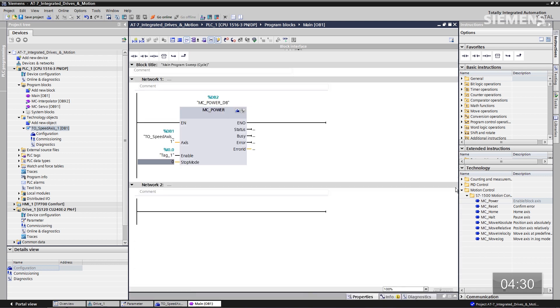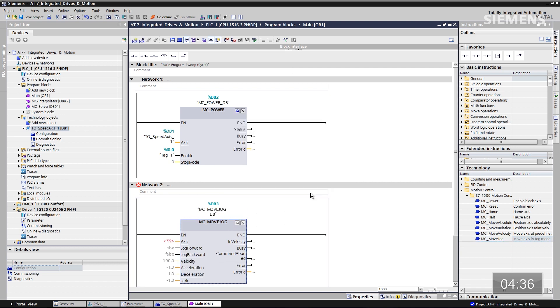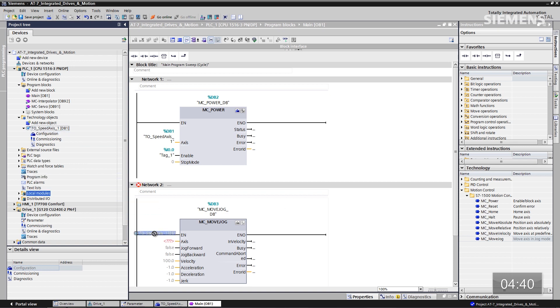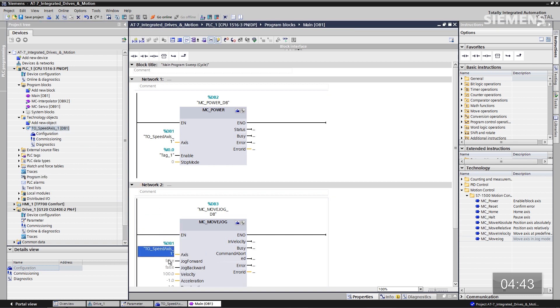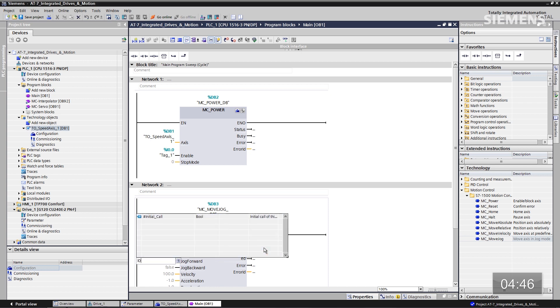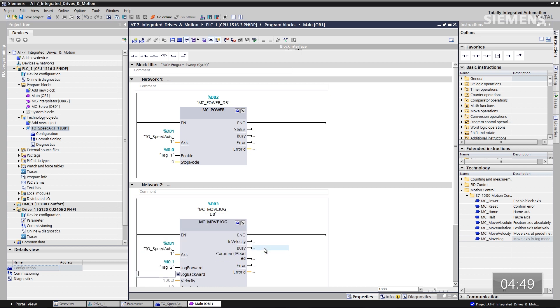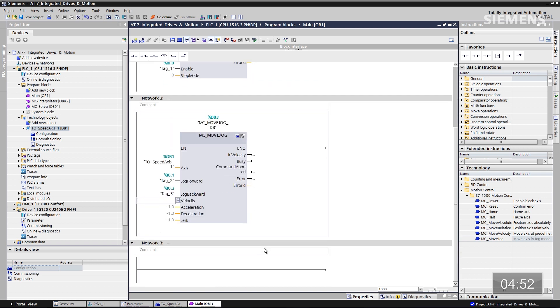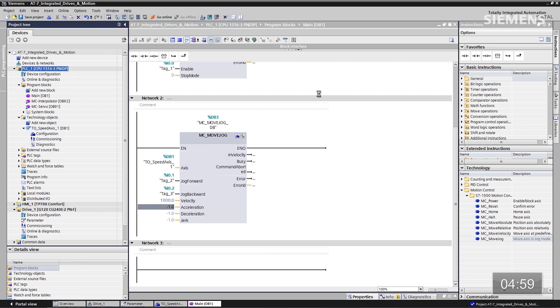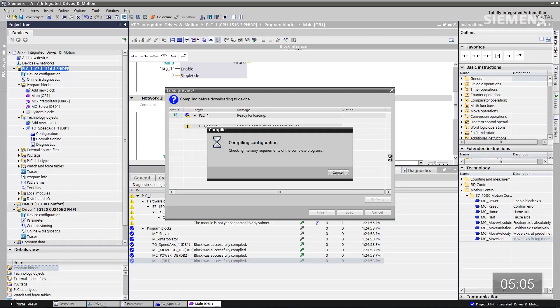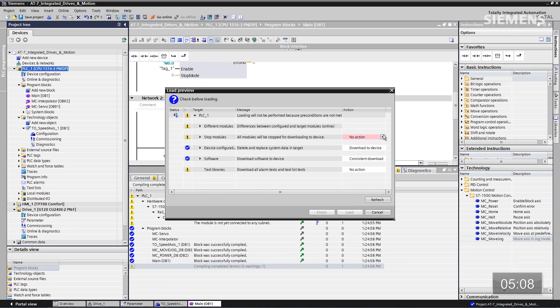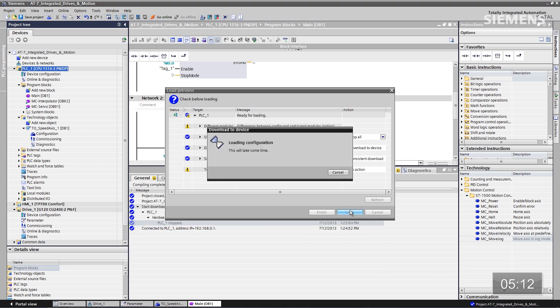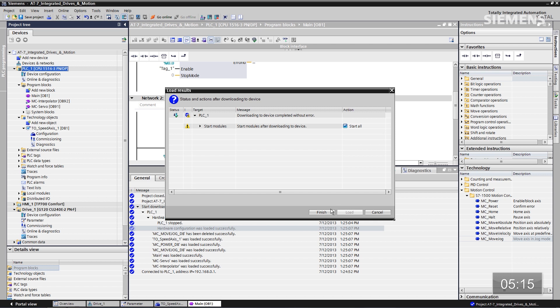Next I want to use an MC MoveJog block. Drag and drop that into our program and accept the default data block. Again, I want to tie this to the TO as well — drag and drop that to the axis input. To go forward I'm going to use input 0.1, to go backwards input 0.2, and our velocity is going to be 1000. Now I give focus to our controller and click the download arrow button. It's going to compile everything for this Motion TO and drive. I can say Stop All, click Load, and it loads to our controller. Once it's complete, click Finish.